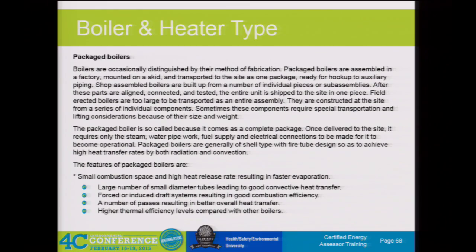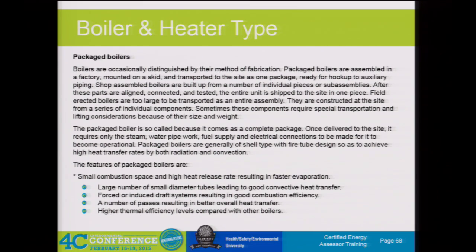Most of the boilers we see these days, unless you're in certain industries, are package boilers. These package boilers come in various sizes but can get up to 250 MM BTUs and greater. A package boiler basically is a design where the boiler ships—it's erected at the boiler manufacturer's shop and comes in requiring basically utilities to be hooked up: steam piping, water piping, fuel supply, and electrical connections. It's a quick easy way to get a boiler on your site and get it up and running. A lot of temporary boilers are package boilers as well.